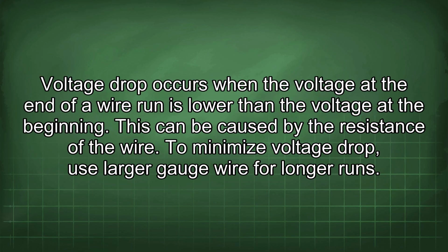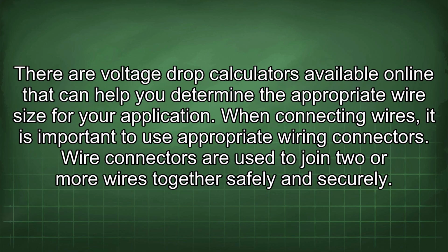Voltage drop occurs when the voltage at the end of a wire run is lower than the voltage at the beginning. This can be caused by the resistance of the wire. To minimize voltage drop, use larger gauge wire for longer runs. There are voltage drop calculators available online that can help you determine the appropriate wire size for your application.